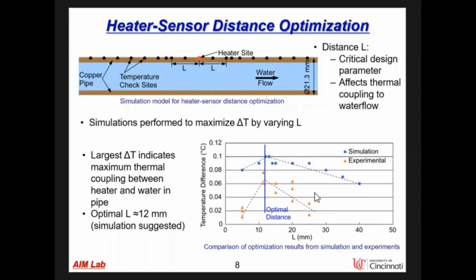The distance L between the heater and the temperature sensors is a critical design parameter that affects the efficiency of thermal coupling with water through the water pipe. Simulations were performed for a series of L values to find the maximum delta T in presence of water flow, as the largest delta T indicates maximum thermal coupling between the heater and water through the pipe. The top figure shows the simulation model on a 3/4-inch copper pipe used for optimization. The bottom image plots the simulated delta T in blue dots at different L values. The optimal length of 12 millimeter was found, and this was compared with experimental optimization results discussed on a later slide.